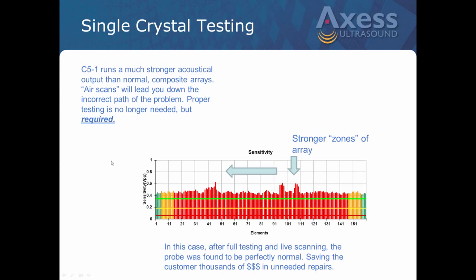Okay, on the C5-1 then, here's the air scan, so you can see they thought they had a problem. Now what we did is when we got the probe in, we were able to actually run a first call with this probe and run it through our testing. One of the things you have to understand about this probe in particular is the C5-1 was developed by Philips to actually do abdominal scanning on obese patients, frankly. They were looking at a way to get clear, precise, clean images on people that had some obesity.